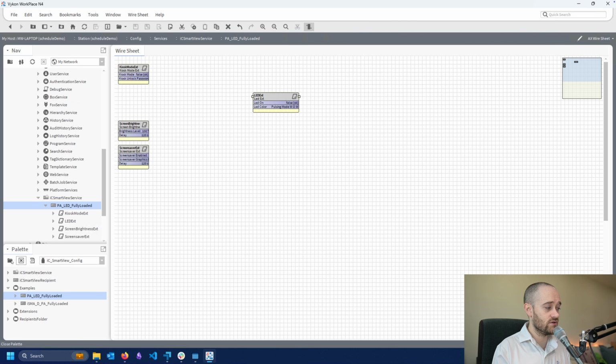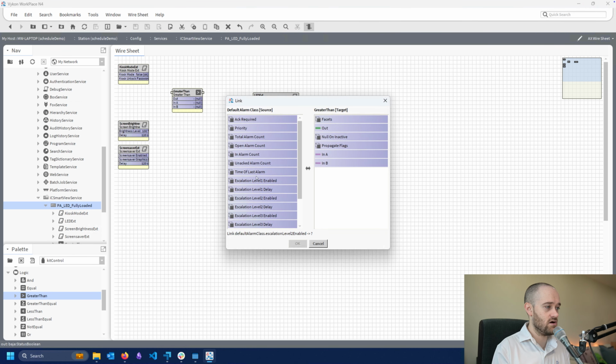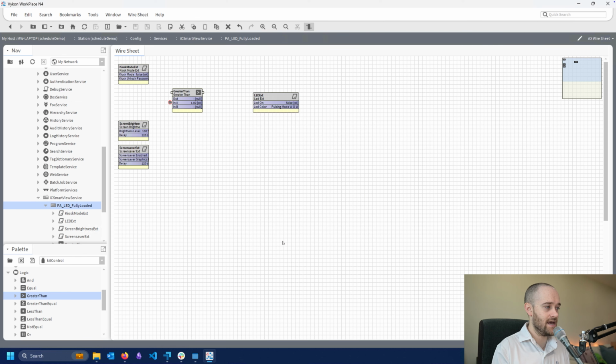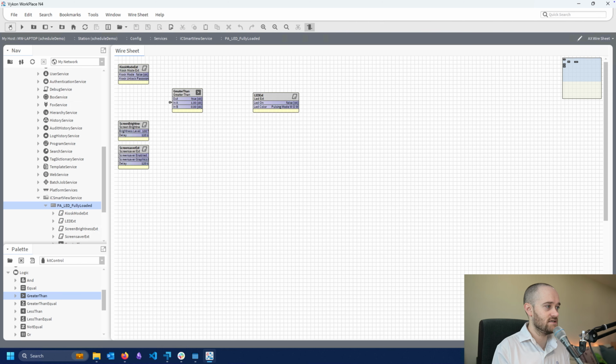So I'm going to go into my kit control, and I'm going to go to logic, and I'm going to pull out a greater than, say OK, and then I'm going to link in from my alarm class, and I'm going to use the Unacked alarm count. I'll go into in A with that, and then on in B, I will just hard code in a 0. And you can see that we're getting the value we expect out of that.